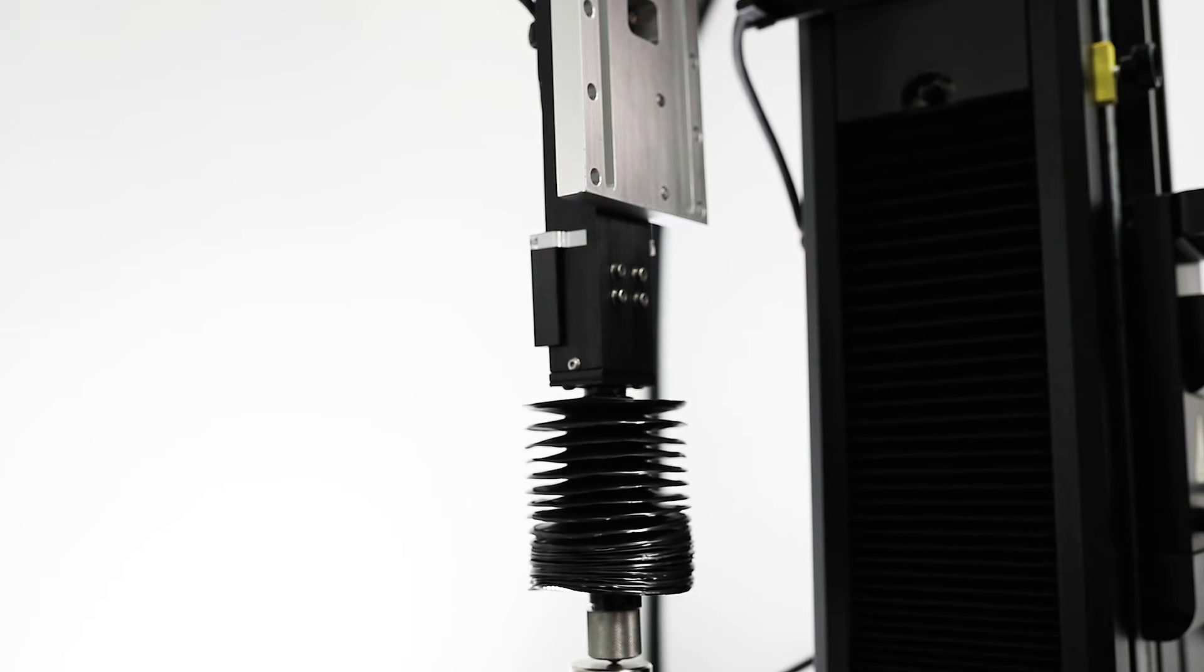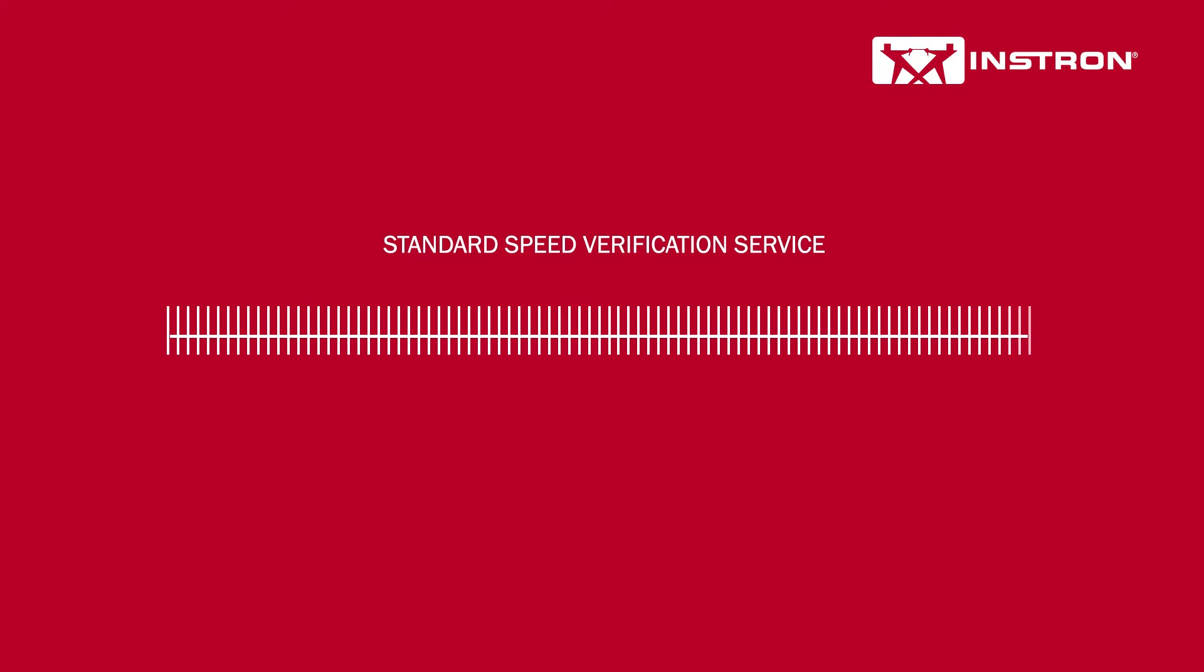Instron's standard calibration service can provide verification of speeds ranging from 1 millimeter per minute or 0.04 inches per minute up to 1,270 millimeters per minute or 50 inches per minute.